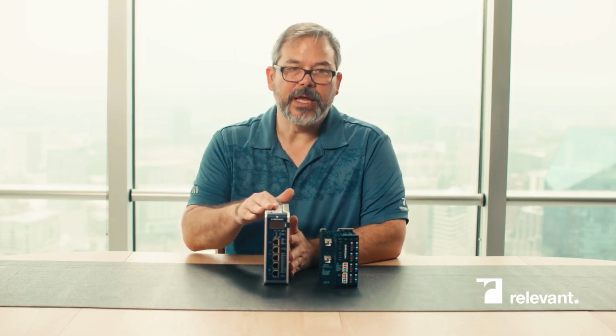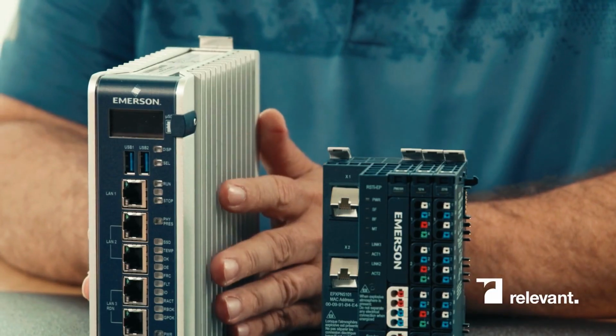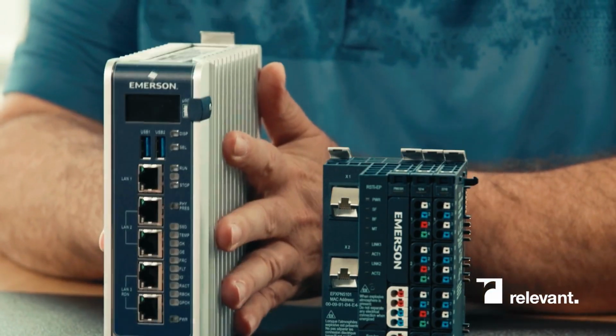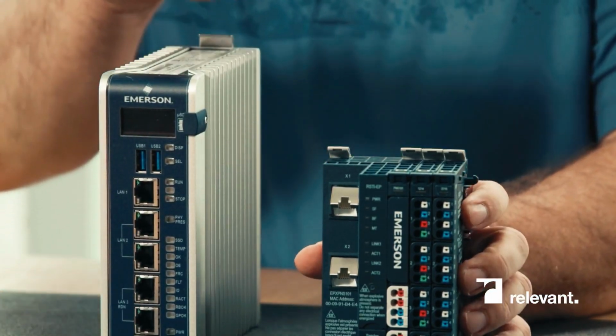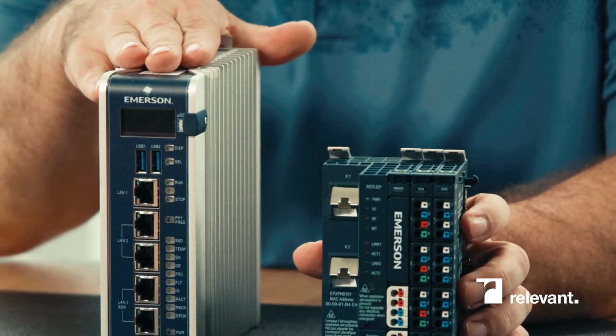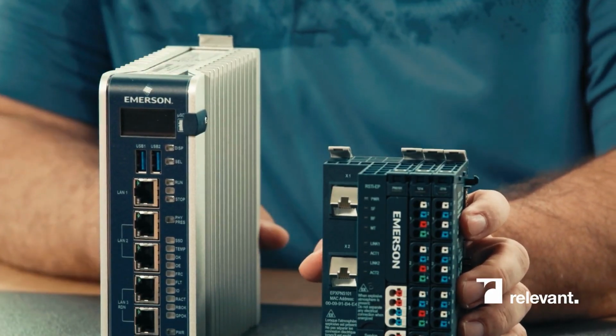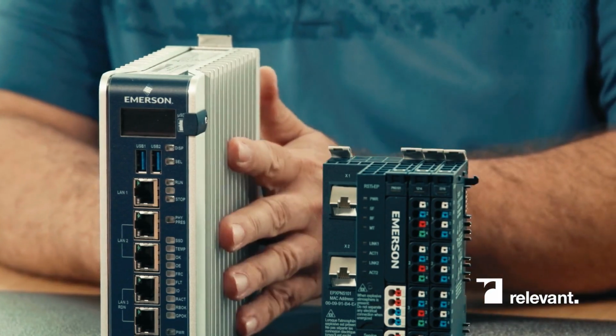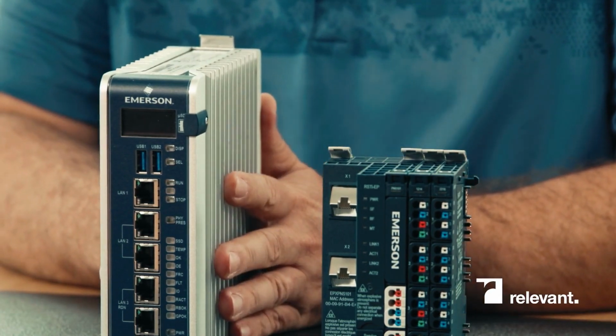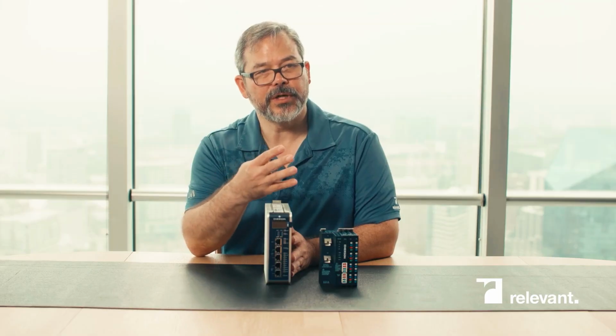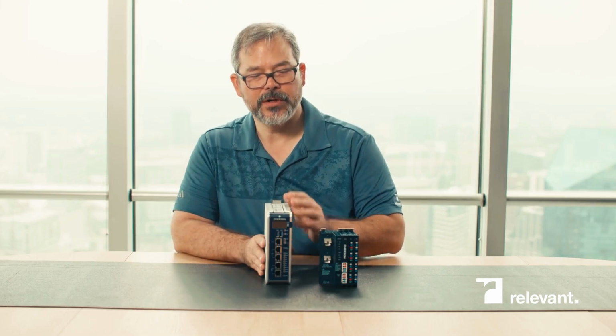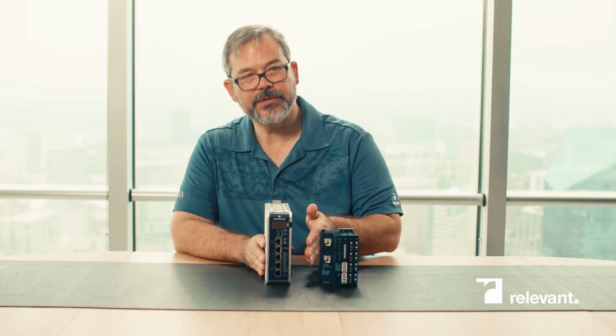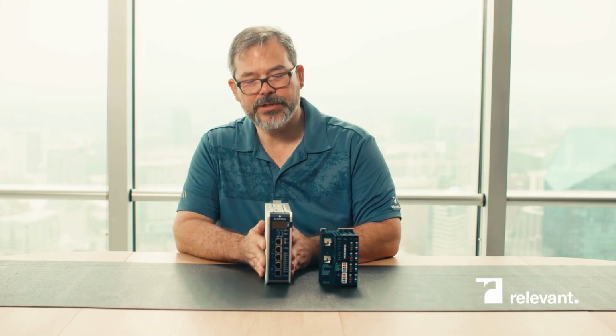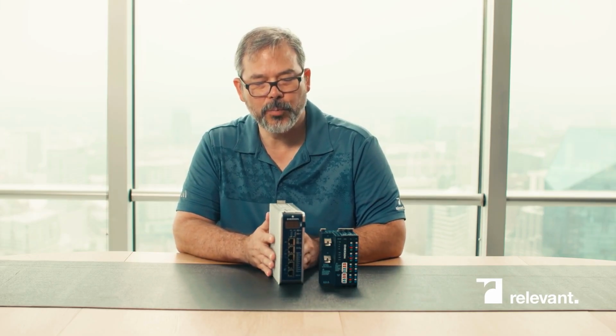What makes this an edge device or an IIoT device is that inside this same box, not only do we have the CPU, the PLC engine, or what we call the PACEdge engine from Emerson Discrete Automation to run deterministic control. In here we have 4 separate cores. 2 of those cores are dedicated to deterministic control, and 2 cores are running a Linux, Ubuntu style, open source operating system.